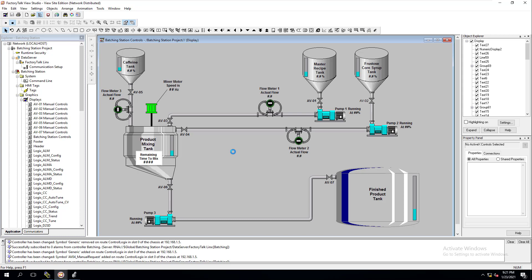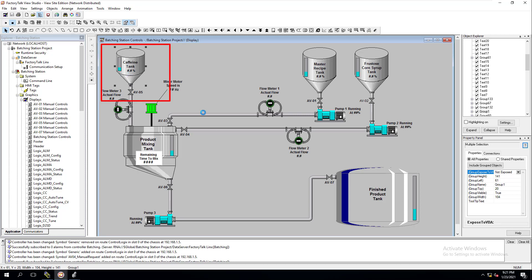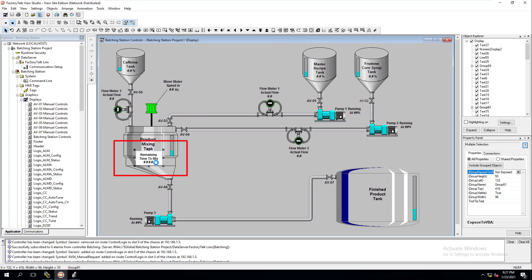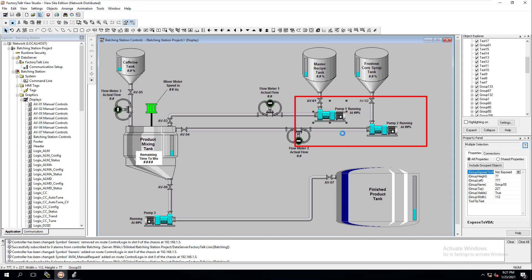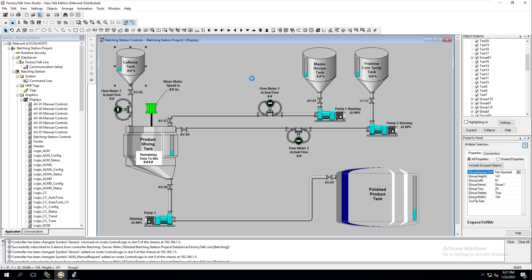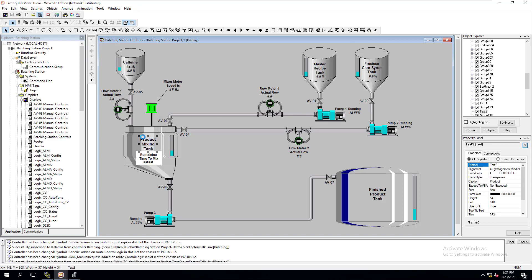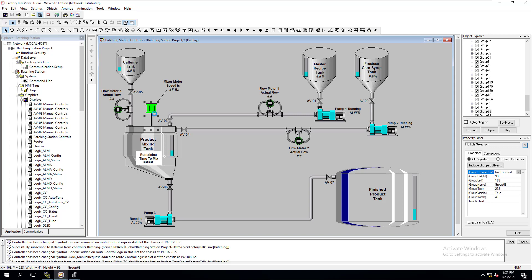What are the key components we want to call up in our recipe? We want to call up the name of the recipe, the amount of caffeine we're using, the amount of master batch we're using, the amount of corn syrup we're using. We also want to call up the time limit of how long the mix should actually be mixing, and the speed of the mixer. Two more key components are the speeds of the actual pumps — so we control the proper amounts of caffeine, master batch, and corn syrup based upon the pump speeds, and then mix that up in a proper amount of time at a proper speed.